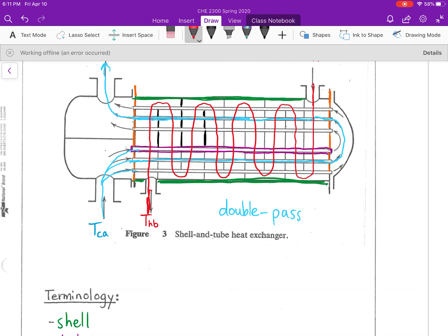The point I wanted to make is that because it is easier to replace the tubes within the shell and tube heat exchanger, we should always pass the dirtier fluid through the tubes, because more fouling is going to occur inside the tubes, and therefore it will be easier to replace a single tube than to replace the entire shell.